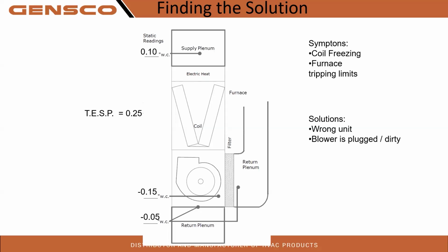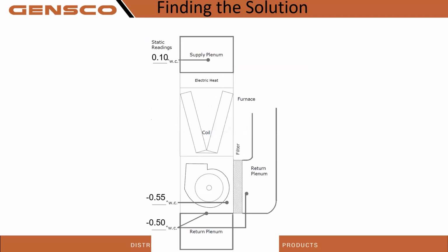We had one where we had a 4-ton system with 8x24 ductwork, 60% less airflow than what it needed. They changed out the electric heat because they thought it was a heat strip failure. No, it was a return air issue. They had to add a return to get enough CFM to energize electric heat because these units are so smart, it's protecting itself. So again, bad or wrong, unit is not capable of developing necessary static.